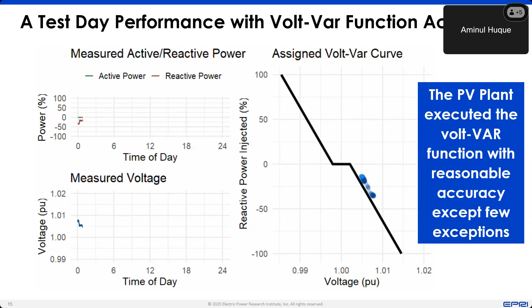But now if we analyze the entire test period, a total of 40 days of testing, maybe 18 of the test days and 22 of the baseline days where we let the plant go into sleep mode with no reactive power support, you are seeing the comparison of the voltage profile for test days, which are green, and baseline days, which are blue.